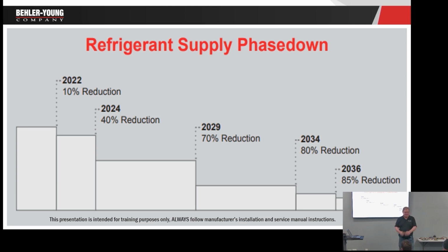The AIM Act, drawing a blank. The AIM Act was signed, which started the phase downs of high GWP refrigerants, global warming potential. Okay, so you'll hear this term GWP, global warming potential. So if you rewind back into the 90s, we were worried about ozone depletion, right? So we got rid of R11, R12, R22, the chlorine. So now they decided that the HFCs that we're currently using, 410A, 134A, 404, 407, all the 407s, all the 422s are HFCs, and they have a high GWP, global warming potential. So 404 has a GWP of over 2,000. CO2 has a GWP of 1. It's the baseline.